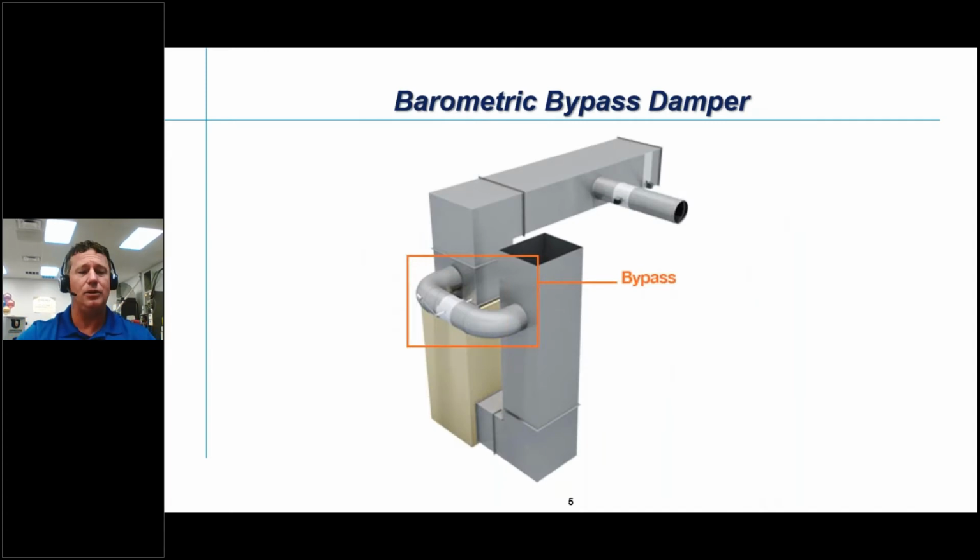It was a completely new atmosphere for me to learn. And so I studied this thing. I had a 16-inch barometric damper on this thing. It was a 5-ton system. Yeah, it was a monster. And later on, I learned exactly why that was so. I had one zone that had like 400 CFM on it, on this 5-ton drive.